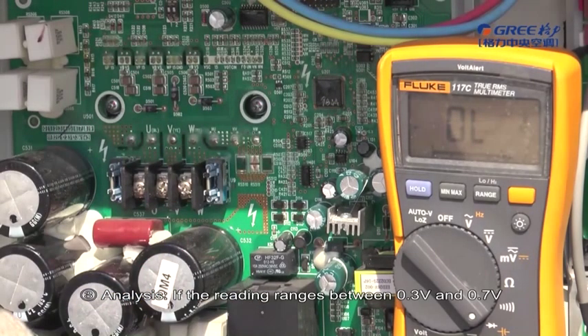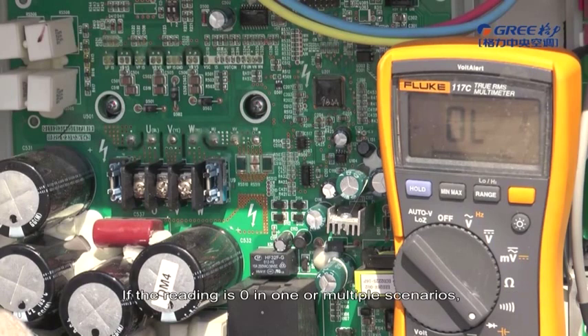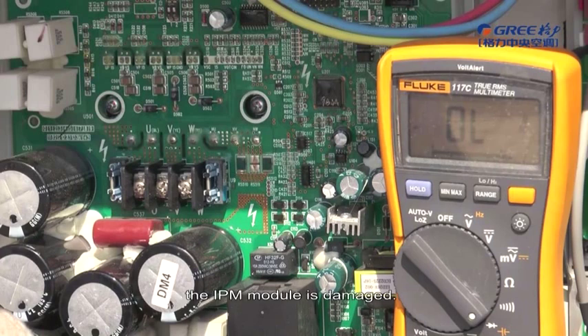If the reading ranges between 0.3V and 0.7V in the above mentioned 6 scenarios, the IPM module is normal. If the reading is 0 in one or multiple scenarios, the IPM module is damaged.